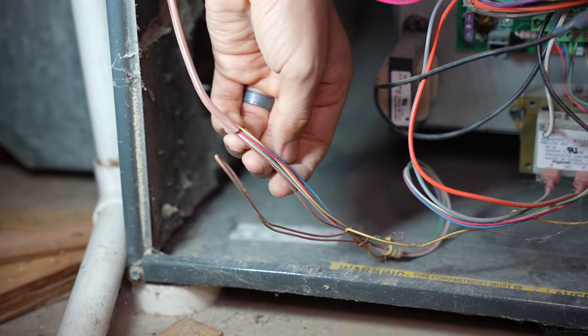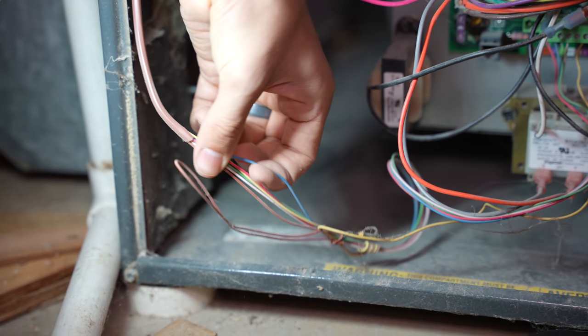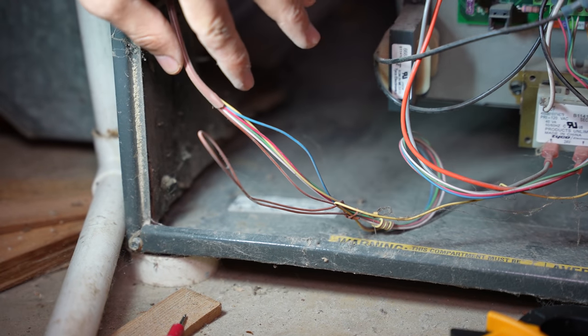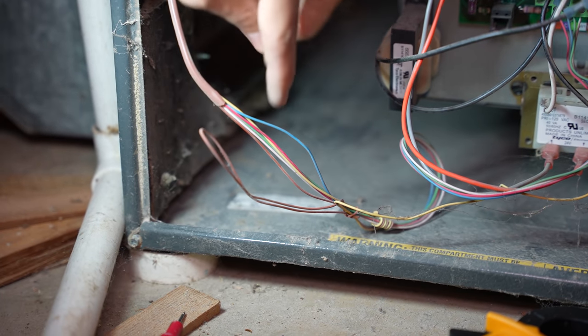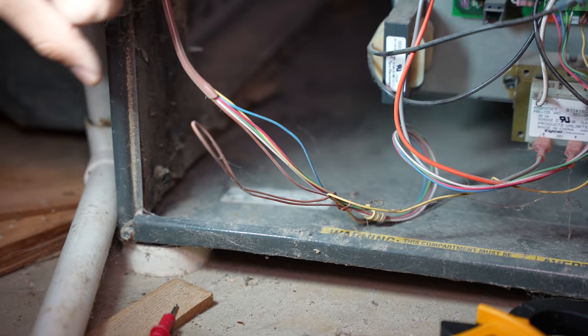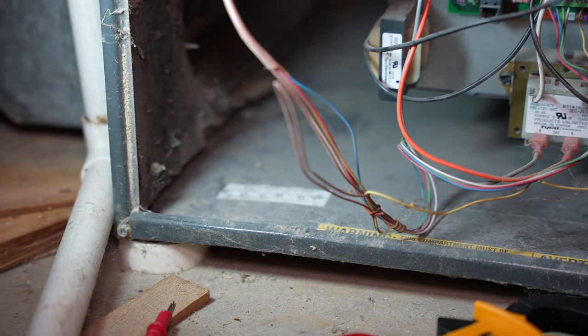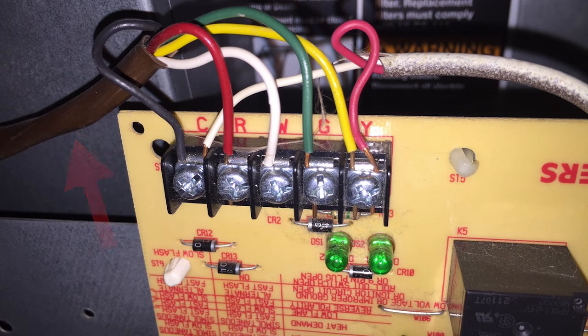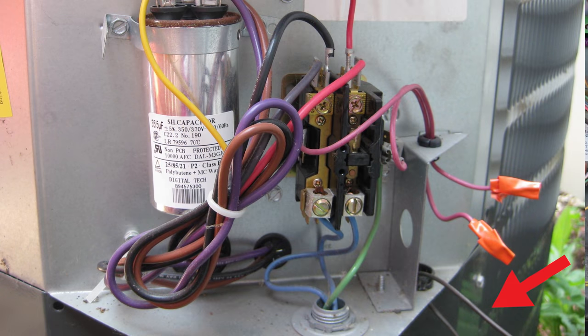If you have a bunch of wires, then the blue wire is usually the common, but like I said, in most furnaces, it's not like this. You just have two wires coming out that are coming from the air conditioner. One of them will come from the thermostat. That one typically has five wires, and you're going to have another one that comes from outside that's only going to have two wires in it, and those two wires are usually red and white. That's coming from the air conditioner.